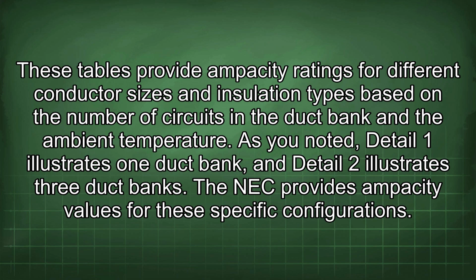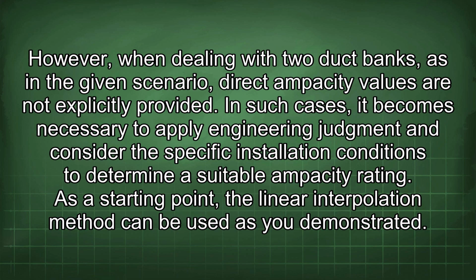As you noted, Detail 1 illustrates one duct bank, and Detail 2 illustrates three duct banks. The NEC provides ampacity values for these specific configurations. However, when dealing with two duct banks, as in the given scenario, direct ampacity values are not explicitly provided. In such cases, it becomes necessary to apply engineering judgment and consider the specific installation conditions to determine a suitable ampacity rating. As a starting point, the linear interpolation method can be used as you demonstrated.